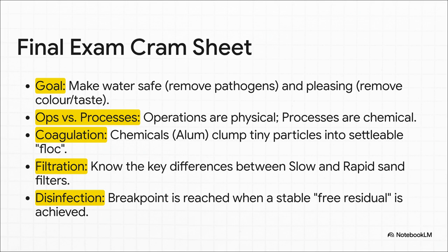Sedimentation lets gravity do the work. Coagulation uses chemicals, especially alum, to make tiny particles clump into floc. Filtration uses sand to polish the water. And you better know the difference between slow and rapid filters. And finally, disinfection uses chlorine to kill pathogens, and the key is to get past the breakpoint to achieve that protective free residual. If you can lock these points in, you've got this.